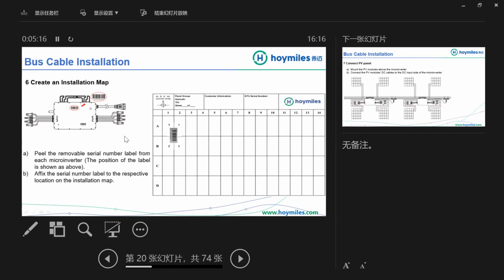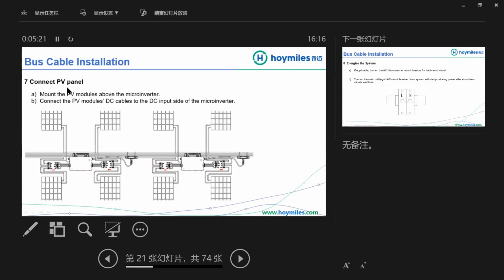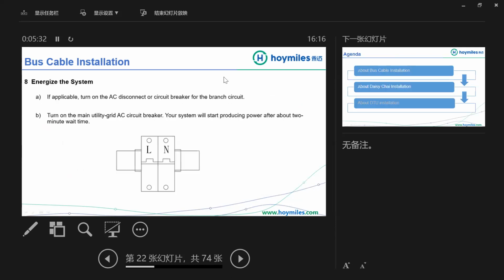And affix the serial number label to the respective location on the installation map. Then to connect PV panel, mount the PV modules above the microinverter. Connect the PV modules DC cables to the DC input side of the microinverter. The final step is energize the system.